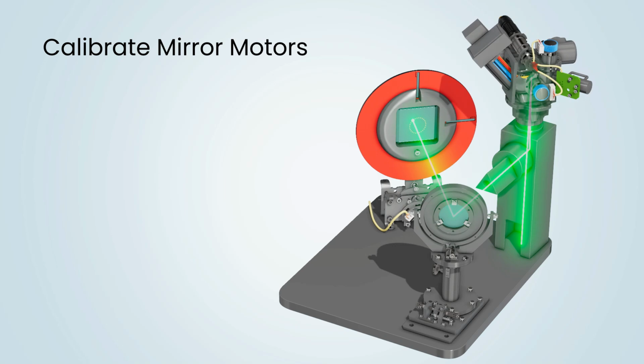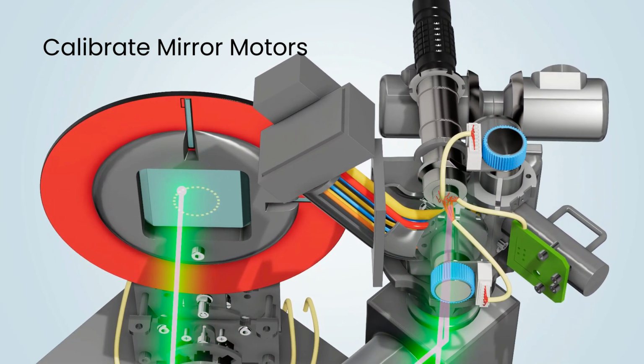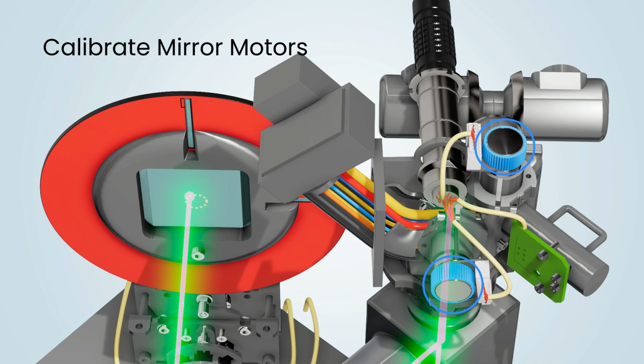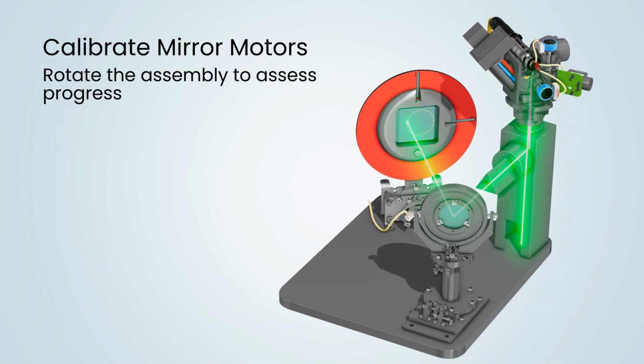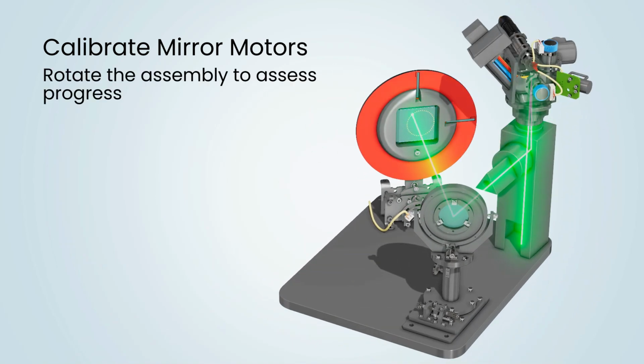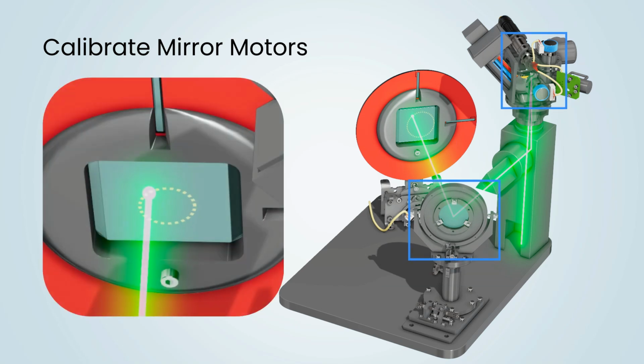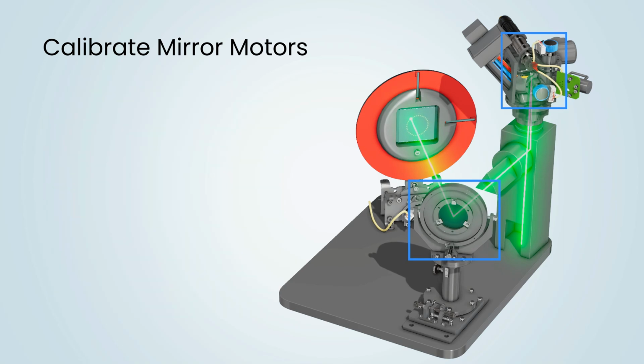If at first you can't see the laser path on the target, adjust the motor knobs to bring the laser path onto the target. Open the locking screws to find the desired friction level. If needed, use a torque wrench. Then adjust the motor knobs until the drift orbit is smaller than the gray circle at the center of the target. Rotate the assembly periodically to check your progress. Use both sets of knobs carefully to bring the laser drift to be as small as possible and centered and inside the gray area at the center of the target. Once a drift of less than 10 mm in diameter has been achieved, you can continue the process.